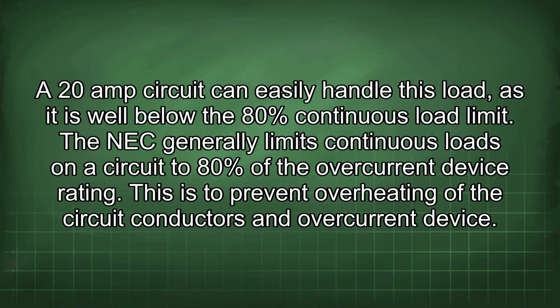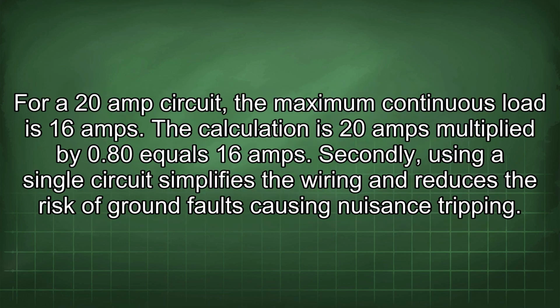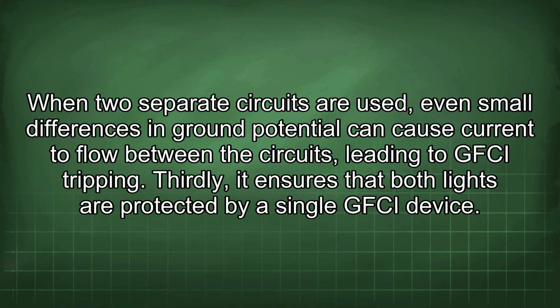The NEC generally limits continuous loads on a circuit to 80% of the overcurrent device rating. This is to prevent overheating of the circuit conductors and overcurrent device. For a 20 amp circuit, the maximum continuous load is 16 amps. The calculation is 20 amps multiplied by 0.80 equals 16 amps. Secondly, using a single circuit simplifies the wiring and reduces the risk of ground faults causing nuisance tripping. When two separate circuits are used, even small differences in ground potential can cause current to flow between the circuits, leading to GFCI tripping. Thirdly, it ensures that both lights are protected by a single GFCI device.